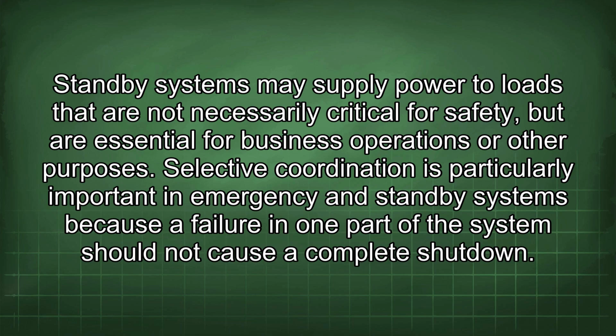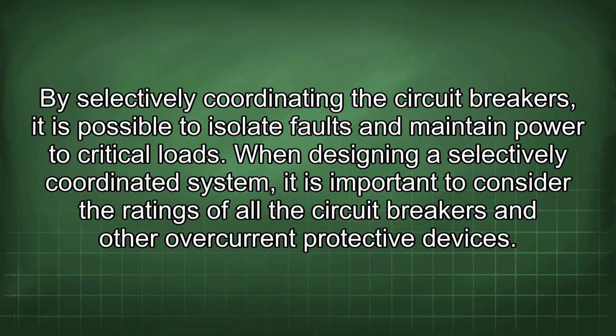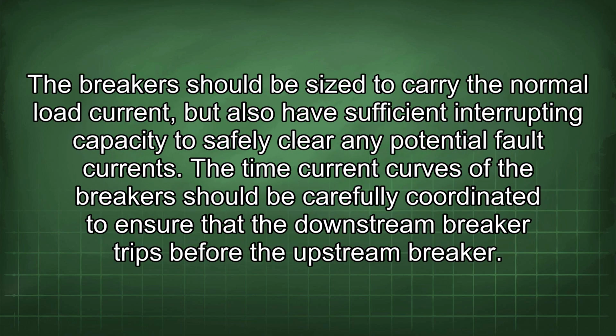Selective coordination is particularly important in emergency and standby systems because a failure in one part of the system should not cause a complete shutdown. By selectively coordinating the circuit breakers, it is possible to isolate faults and maintain power to critical loads. When designing a selectively coordinated system, it is important to consider the ratings of all the circuit breakers and other overcurrent protective devices. The breakers should be sized to carry the normal load current, but also have sufficient interrupting capacity to safely clear any potential fault currents.